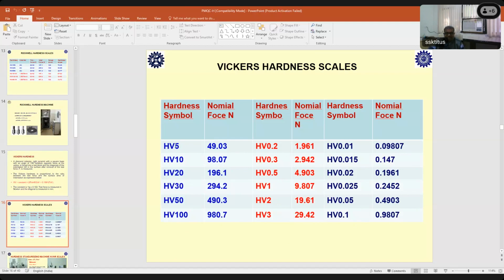So this HV5 means we are applying a force of 5 kg. Here there is no concept of preliminary force and total test force. Here we have to apply the total 5 kg force on that sample using the pyramid indenter, then release that force. But how much time? Here there is a tolerance of 10 to 15 seconds, as the standard gives. So you have to define how much time you are applying that standard force on the sample using the pyramid indenter. Then you release that force, put the sample under a high precision microscope and measure the diagonal.